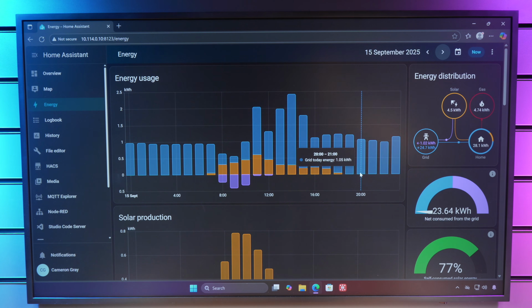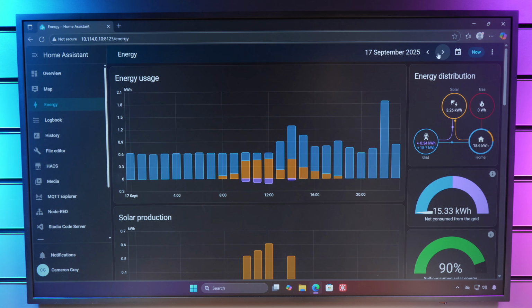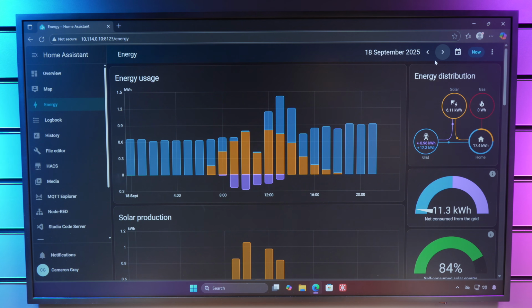The final thing I did was taking a look at my usage pattern compared to my energy provider's app from that test I did where I tried to smooth the data out, and it was better than what we see here, where my calculation with my smooth data, I estimated 15.7 kilowatt hours from the grid. According to my energy provider's app, I drew 16.37, so a lot closer. But the difficulty is with that smoothing being so impacted by the power factor on different circuits, it could wildly change depending on what sorts of loads I'm using, so it's not really accurate. So at least now with this setup, I am getting decently accurate stats across my grid, solar and socket circuits, but I'm not really able to monitor those other circuits like I really want to be able to do.